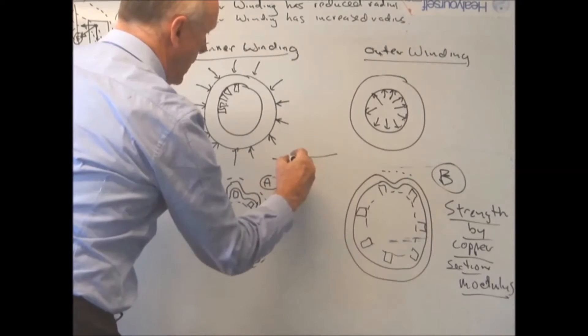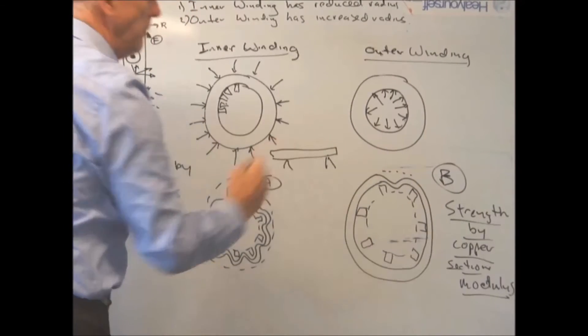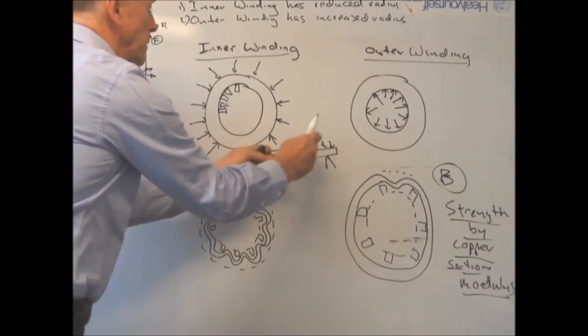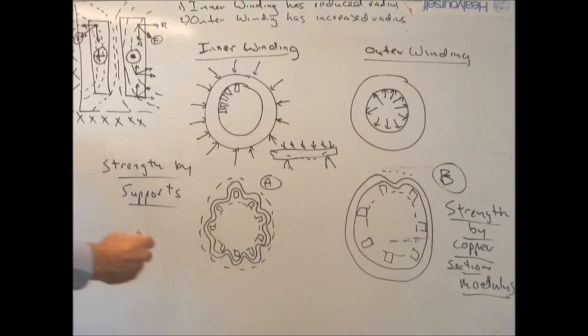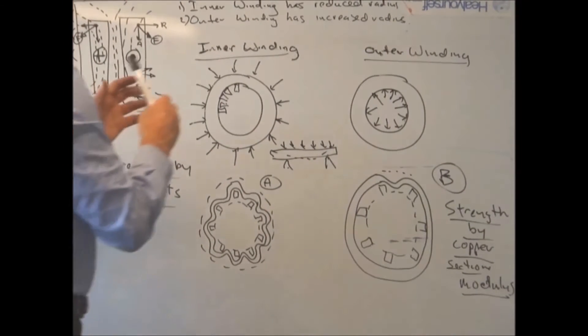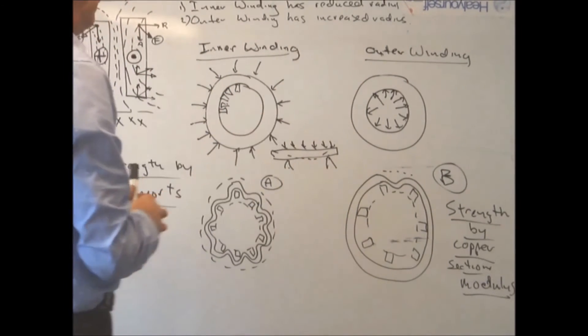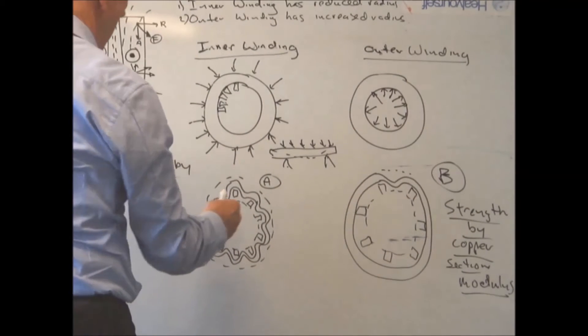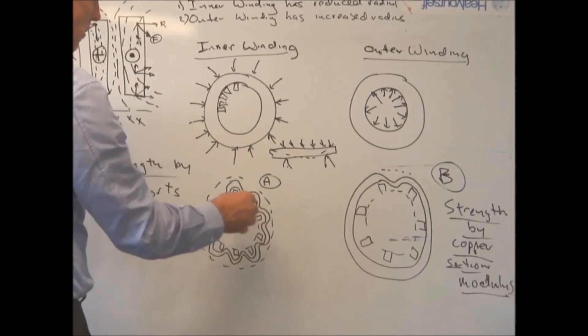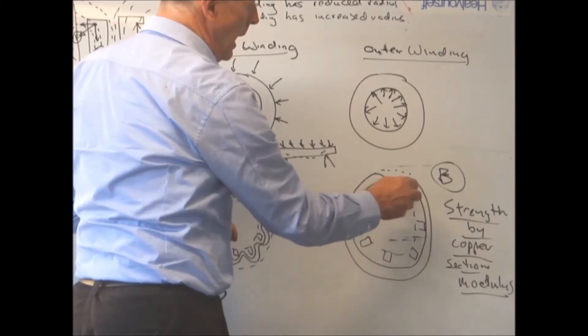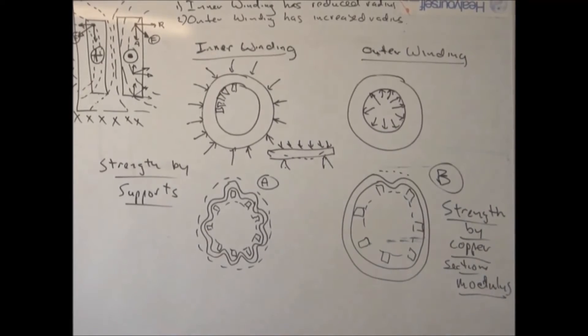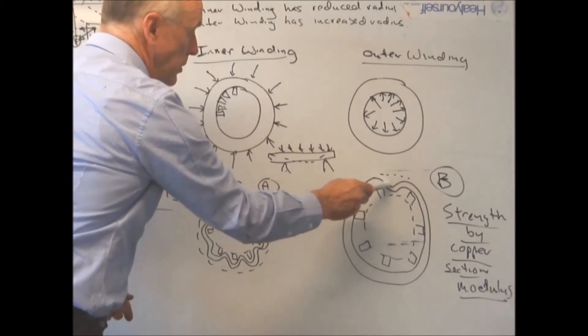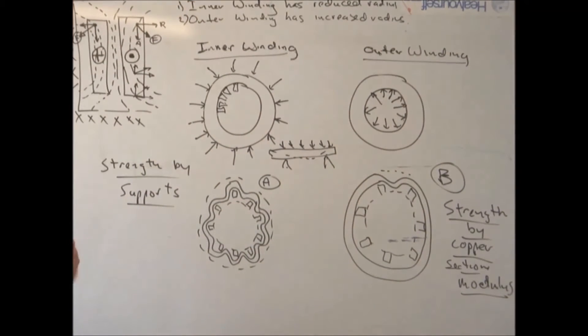It's just like in mechanical engineering where you have two support points and a beam with constant force — by reducing the span you reduce the deflection. So we've determined that the inner winding compresses and the outer winding expands. Looking at typical failures, one type is caused by not enough supports, and another is due to inadequate section modulus or strength of the copper. By looking at whether a failed winding has a single bulge or multiple loops, you can determine what caused the problem.